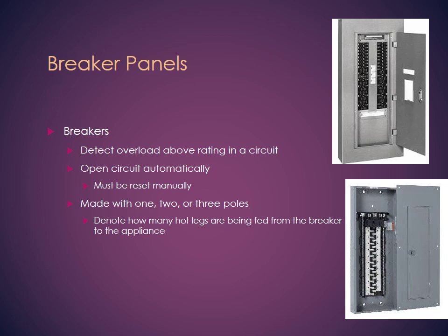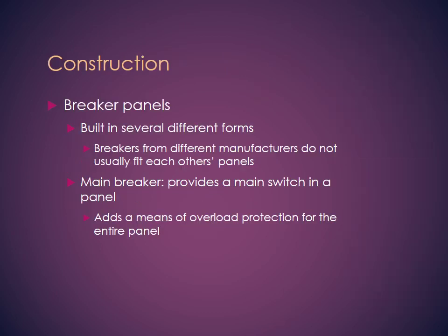Breaker panels, again, if you look here, this is where you clip your circuit breaker, and you see this is the hot line and this is our neutral. So if you have a double breaker, probably to clip in two hot lines, they call those lugs because they can clip to them. And breakers detect overload based on the rating. If it's 15 amp, if we draw 17 amps or 16 amps, it will trip. So you can go and reset it manually. They can be 1, 2, or 3 poles depending on the setup of these breakers and how many legs there are. So one pole could be for 110, 2 poles 220, or 3 poles could be more than 220, or could be 3 phase. They are constructed in different ways.